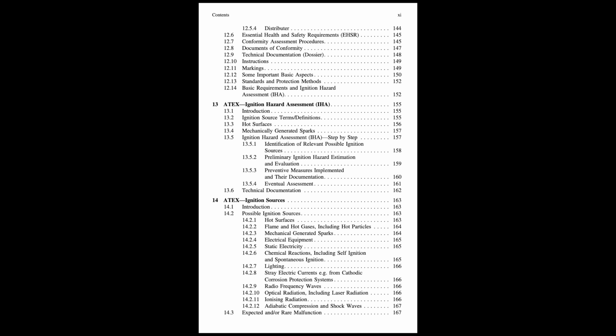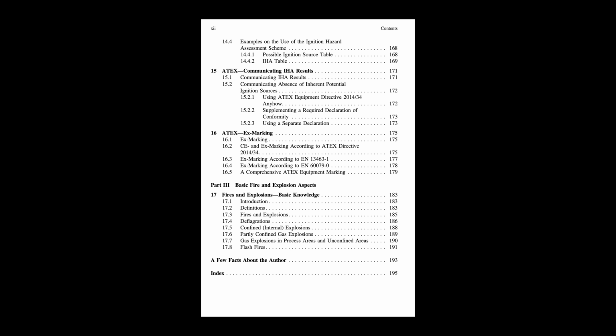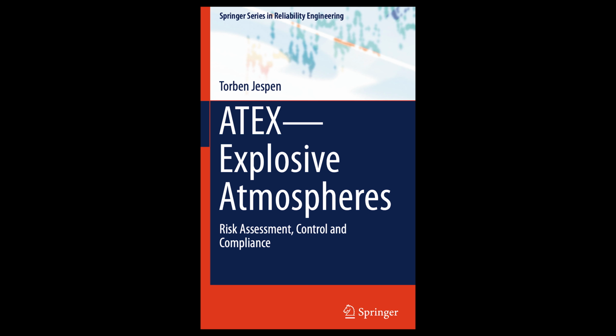What about ignition temperatures for dusts? Is it just like AIT for gases? There are actually two main ignition temperatures for dusts you need to worry about. First is the minimum ignition temperature, MIT, of a dust cloud. That's similar to the auto-ignition temperature for gases, the lowest temperature of a hot surface that can ignite a dust cloud floating past it. Okay, MIT for the cloud. What's the second one? The second is the layer ignition temperature, or LIT. This is the lowest temperature of a hot surface that can cause a layer of dust settled on that surface to start smoldering or glowing. Ah, so dust just sitting on hot equipment. Yep.